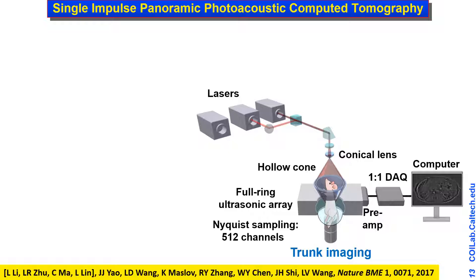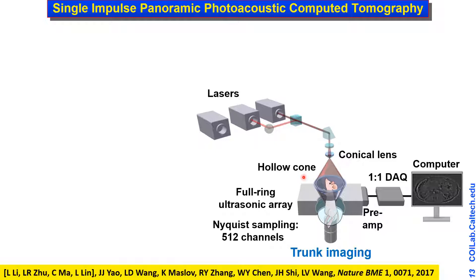The 2003 work used a single-element ultrasound transducer that took about 20 minutes to acquire a 2D cross-sectional image — too slow for many applications. We then developed a single-shot configuration using a conical lens to expand the beam into a hollow cone to deliver light to the trunk area efficiently. A full ring of transducers views the object from all possible angles for the best image quality. We follow the spatial Nyquist sampling criterion using 512 channels to minimize aliasing artifacts.